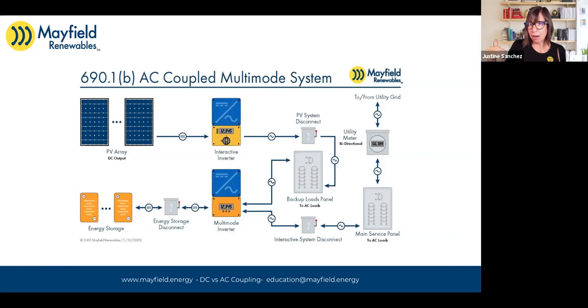When we've done our design to add this storage system, we're going to think about what we want to keep operating when the grid is down. Those are the loads that get moved from your main service panel over to a backed up loads panel. And now you have a pathway.